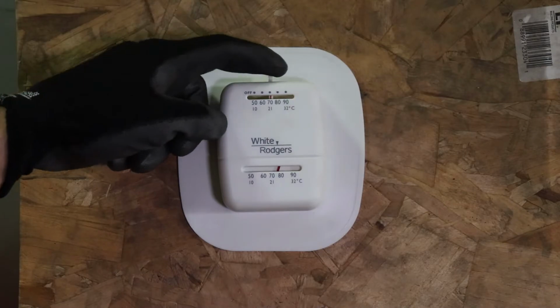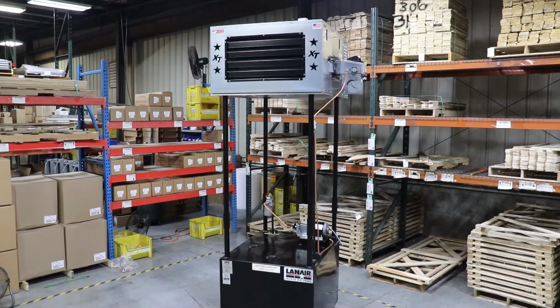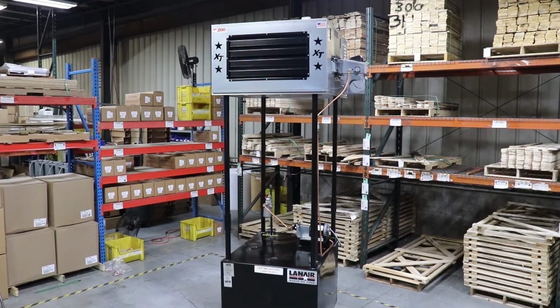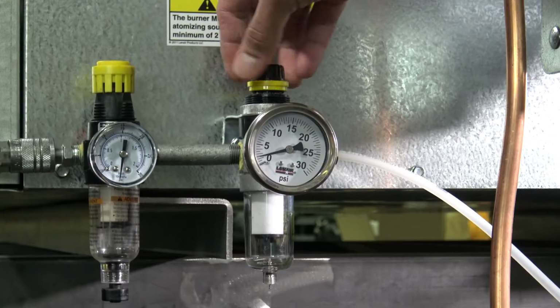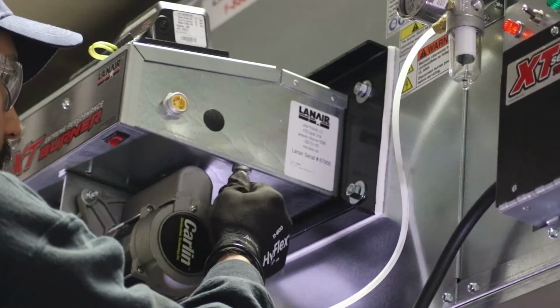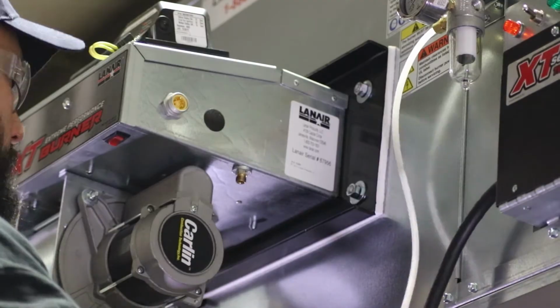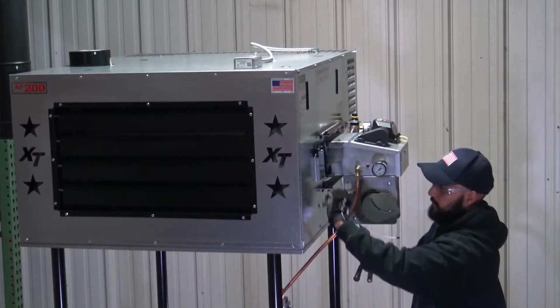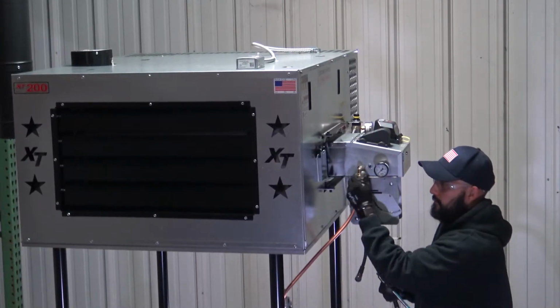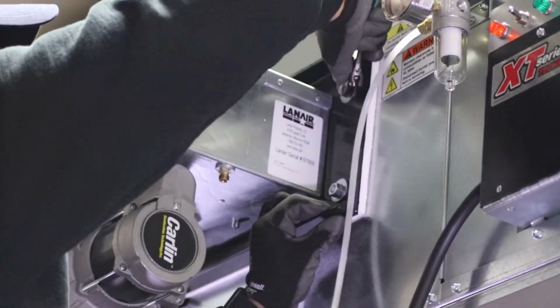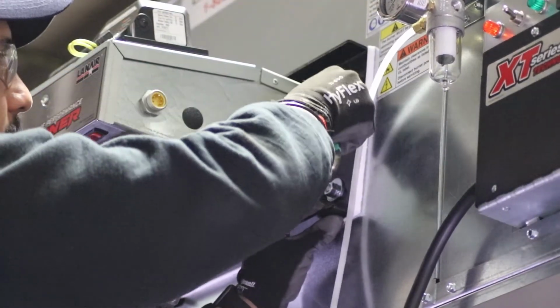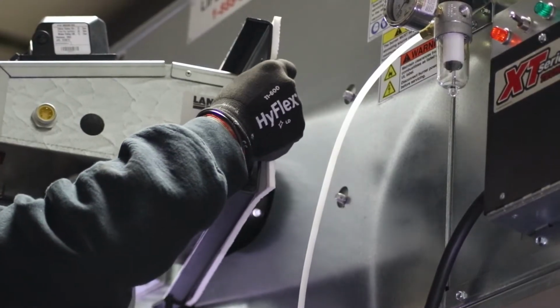Set the thermostat to its lowest temperature setting and turn the power to the heater off at the building's circuit breaker. Set the secondary air pressure regulator to 0 psi and remove the air supply line from the burner. Disconnect the burner cord and fuel supply line from the burner as well. To change or service the nozzle, remove the nuts mounting the burner to the cabinet and swing the burner away from the cabinet on its hinge.